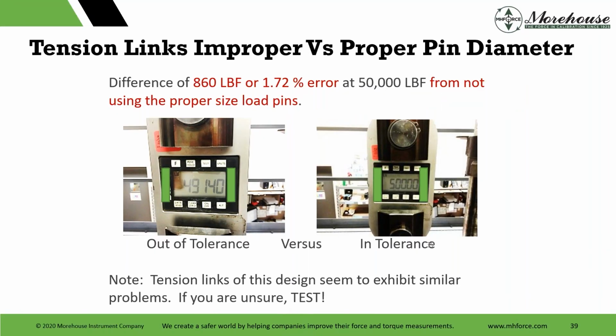Another example, this is one I use all the time, tension links, because people do them. Hey, 2 pin sizes, and the customer doesn't send in what they're using it with. There's a manufacturer's specification. If the lab doesn't use the recommended, I think it's an E diameter, it might be F diameter, of whatever the pin is, there could be extreme errors. Here's a difference of 860 pounds or 1.72% error on a device that's supposed to be 0.1%. You can test this. If you run a cal lab or you have equipment, you can rotate your pins around in the tension link, or you can test it by using safer pins or loading it to half capacity and just varying that pin size. You most likely would see quite a large difference depending on the design of the tension link.